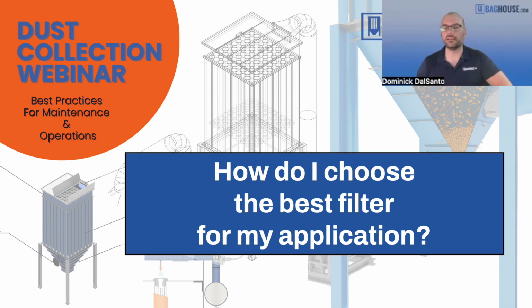Yeah, good explanation, Scott. Thanks. I would just add too, there's sometimes where we have applications where there's multiple fabrics and things that will work, and sometimes it's a cost benefit analysis. Or then in other applications, there's just alternatives or add-ons we can do. For example, we might add a coating or a treatment, perhaps that'll help with the dust release. We might add a coating like an oleophobic coating to help repel some moisture and oils that are in the gas stream. Maybe not essential for operation, but can make things work a little bit better for a reasonable upcharge in the price, right? And then the cost benefit analysis can make sense there.